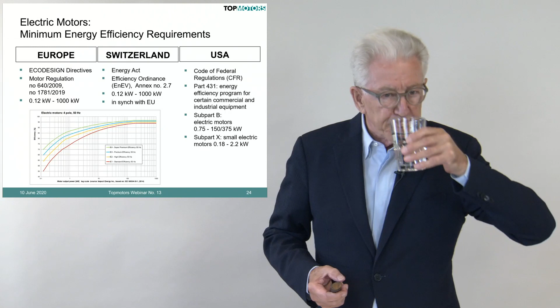Now, I quickly show you 3 types, 3 countries or groups of countries, and I show you the minimum energy efficiency requirements for motors. On the left side, Europe. Europe has an Ecodesign directive. It has a motor regulation that has been well known since 2009, number 640, also used in many Asian countries. And now it has just issued a new one, 1781. It was published last year and starts to be enforced from 2021 on. And it covers the whole range between small ones, 0.12, and 1,000 kilowatt.